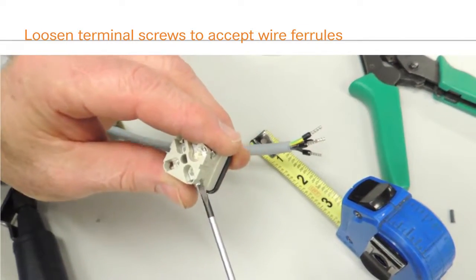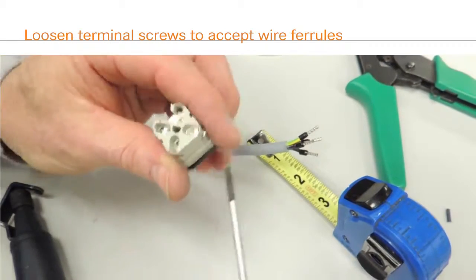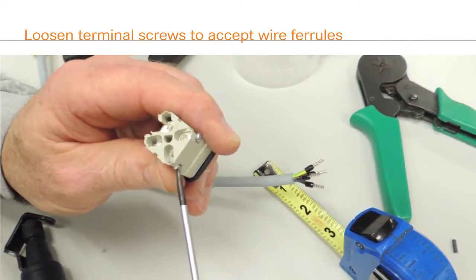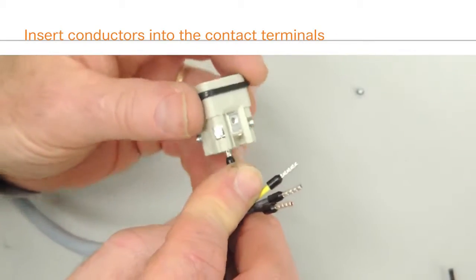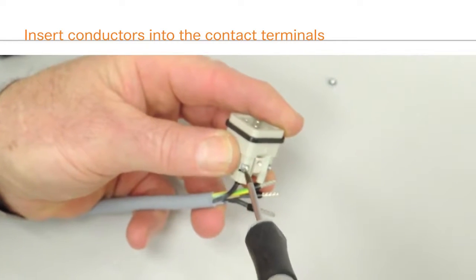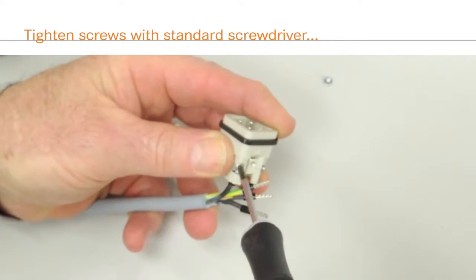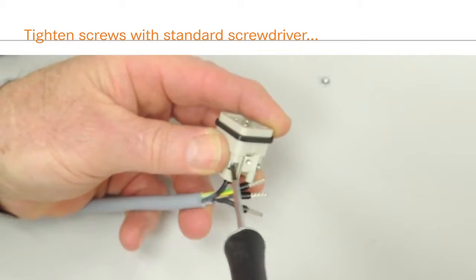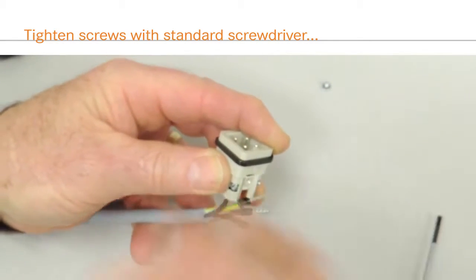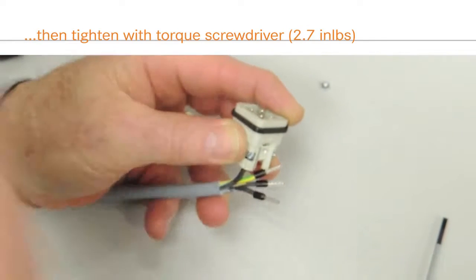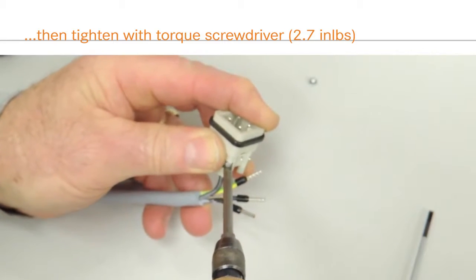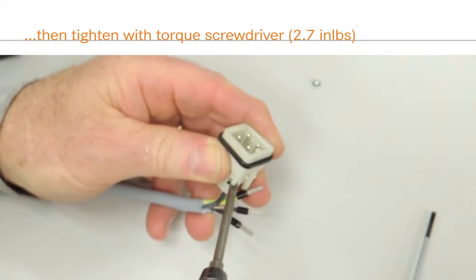Loosen the terminal screws on the insert in order to accommodate the conductor ferrules. Insert the conductors and tighten with a screwdriver. Follow this with a torque screwdriver set to 2.7 inch-pounds. Repeat for the remaining conductors.